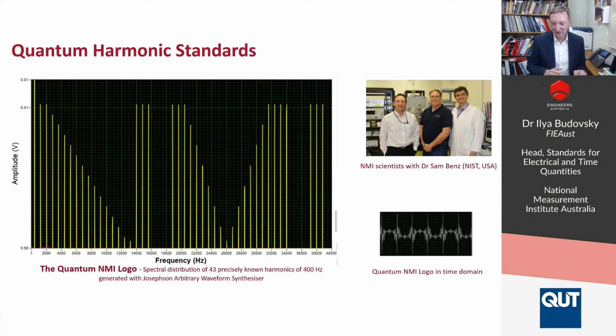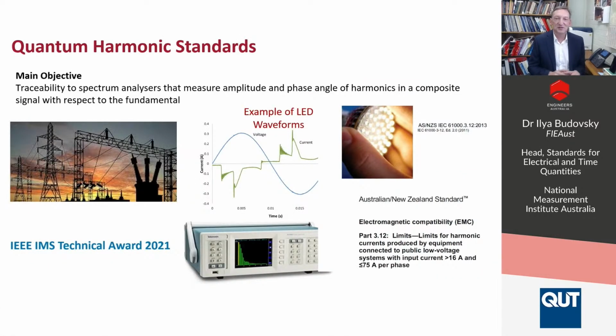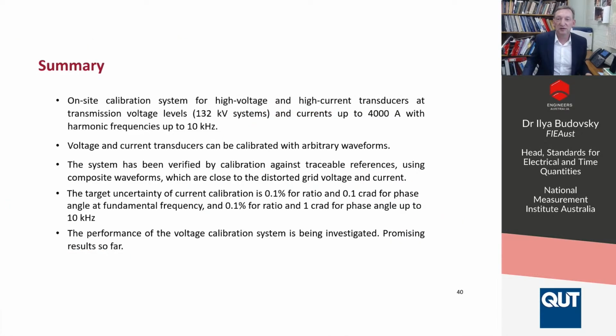Of course, this quantum NMI logo is not useful in its own right, but what's useful is that we can create any waveforms, such as the ones that we would use for this project. And here's just an example of a waveform that is very typical for light-emitting diodes and solid-state lights. And just by the way, this work was awarded by the IEEE Instrumentation and Measurement Society, a technical award for 2021. So these quantum standards we will use to calibrate, or we're already using to calibrate, the digitizers that are used in this system. So they are traceable to quantum standards and to essentially signals with unlimited accuracy.